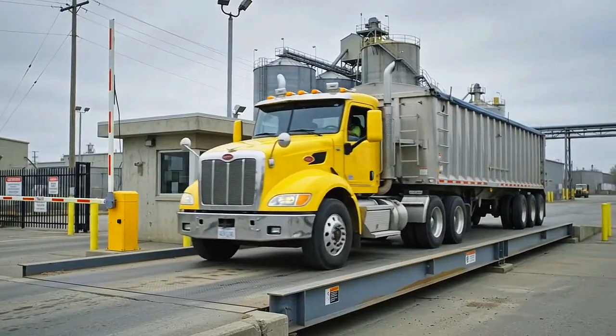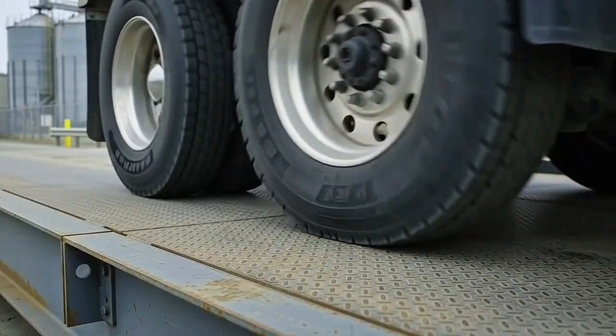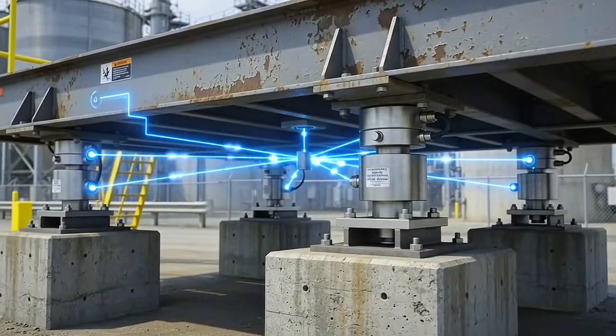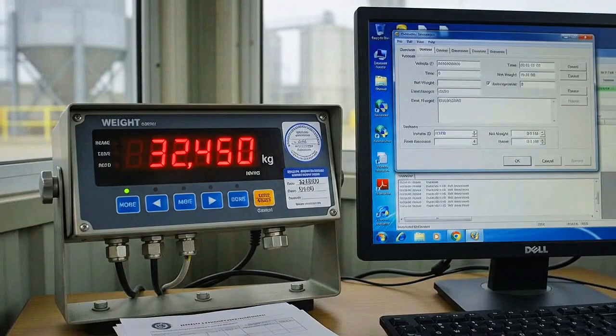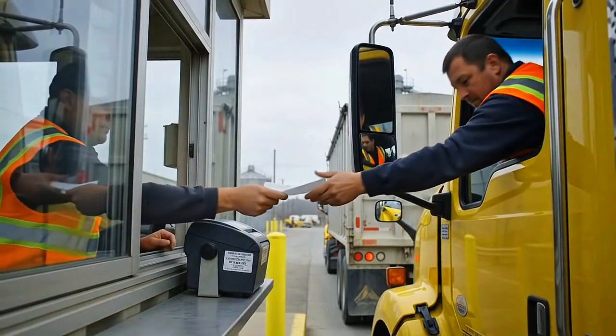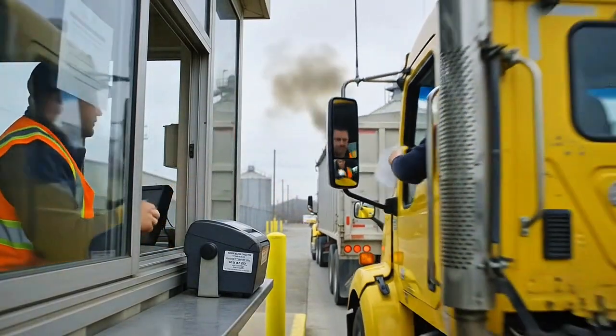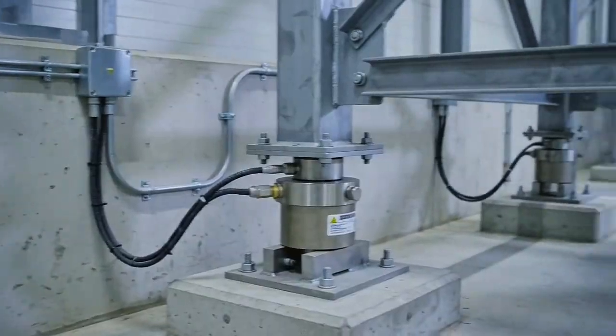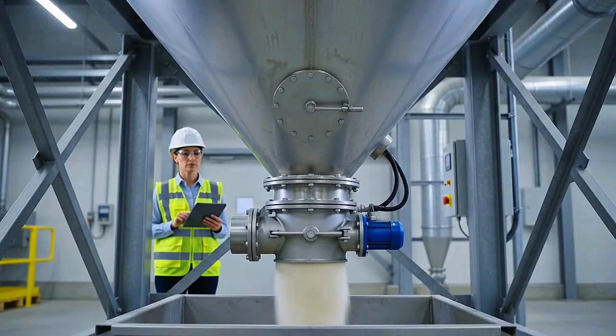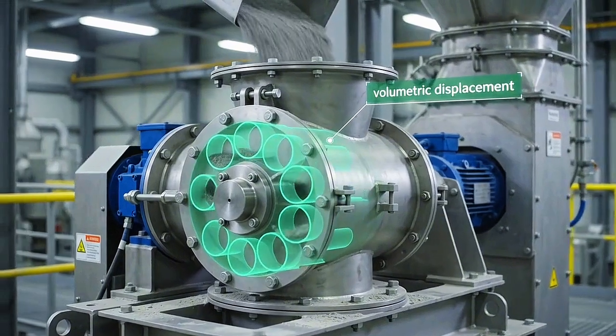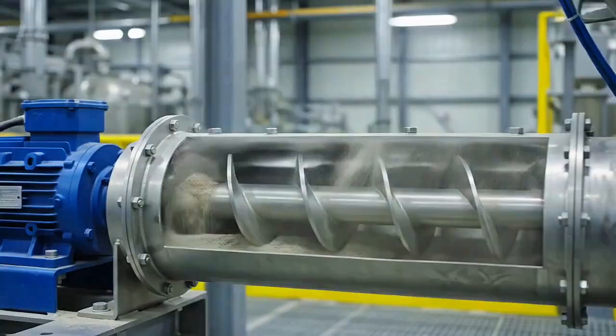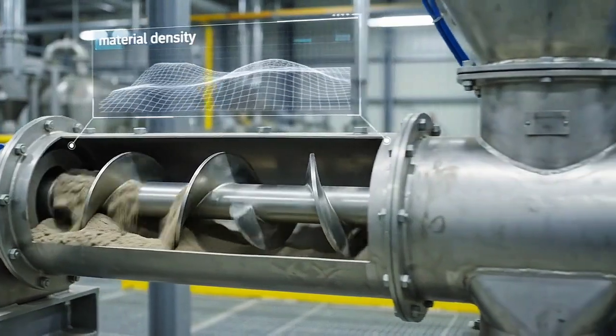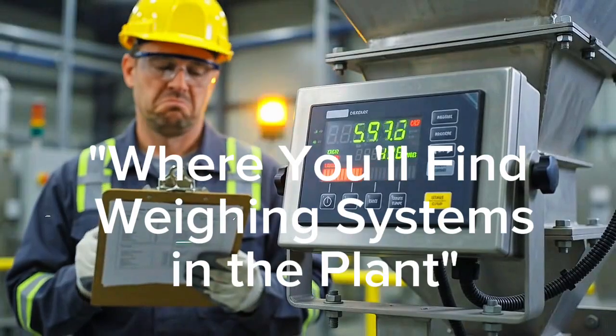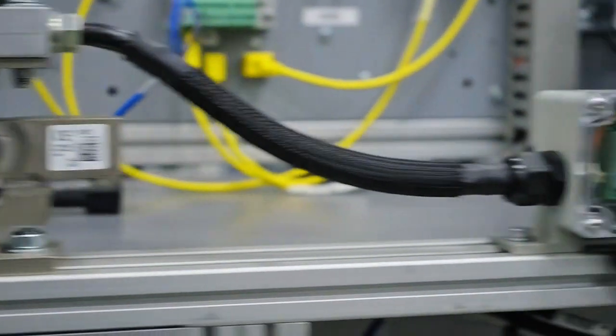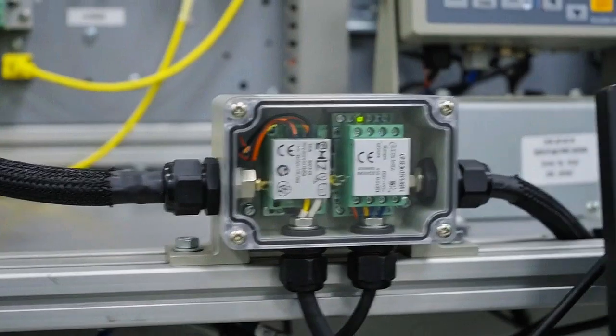Weigh bridges, the truck scales at your gate. Multiple load cells under a single deck, summed together, used for commercial custody transfer. These carry legal metrology requirements because money changes hands based on that number. Hopper and silo weighing, storage vessels sitting on 3 or 4 load cells, used for inventory tracking and sometimes for batch dosing. Rotary and screw feeders, where you're inferring mass flow from volumetric displacement and material density, which brings its own calibration headaches. And behind every one of these, the same signal chain: load cell, junction box, cable run, indicator or transmitter, and finally your PLC or DCS.